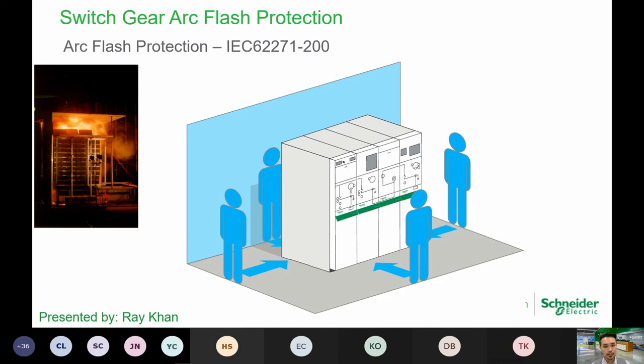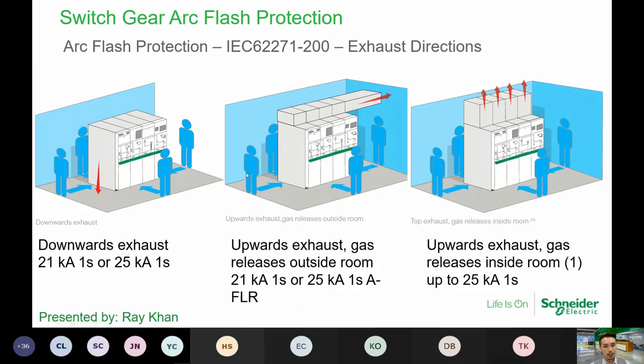Right, so they will inject an arc, for example, based on 25 kA, 1 second. Right, so that's why they put the cotton materials around here, to simulate a person standing there, to see if they are being hurt or can be injured. All right, so the purging can be upwards or downwards. You can see that here is an up purge, and this picture is a down purge, a down exhaust. Okay, so once it's purged, it goes up, or it can be to the side as well. So there are different exhaust systems in place.